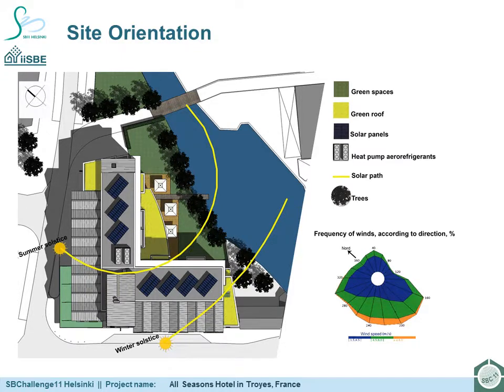The site is relatively open to the south, allowing the building to benefit from solar heat. The site is exposed to the sun for an average of 1,771 hours per year and receives 1,300 kilowatt hours per metre squared per year of solar energy on a horizontal surface. The internal layout of the building is designed to optimise the comfort of the occupants and reduce energy usage. The reception, bar and restaurant can be found on the ground floor. The main entrance is situated on the northwest facade and protected from the dominating wind from the southwest. The main entrance doors are accompanied with a SAS to avoid uncontrolled airflow, hot or cold, into the building. The bar and restaurant, which are only used in the morning for breakfast, are orientated towards the east, are connected to an outside terrace and benefit from the morning's solar rays.